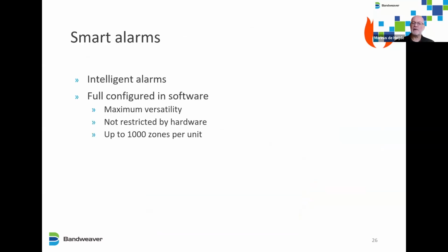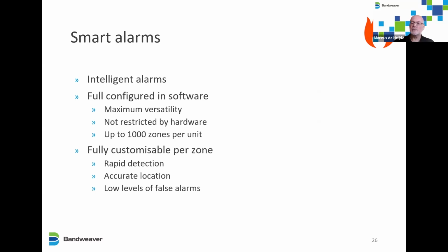A little bit about the smart alarms we've already mentioned. We also call them intelligent alarms. They're fully configurable in the software, maximum versatility with overlapping zones, different alarms in different zones. It's not restricted by the hardware, and we can have up to 1,000 zones per unit. And all these zones are fully customizable, so we can have different types of alarms in different zones. You can have shorter zones or longer zones, overlapping zones. As I mentioned, it's completely configurable in the software. And this customization gives you rapid detection, accurate location, and low levels of false alarm.